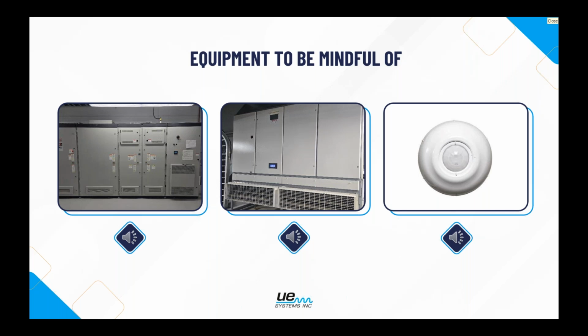The example that I have here in the middle is to be aware of fans especially. Here we have a fan in the room that, if we were not aware of it and had been inspecting other pieces of equipment, there was actually a damaged blade inside of this fan that was rattling around rather aggressively. And if that had reflected off another piece of equipment, it actually could have been mistaken for tracking, possibly with mechanical looseness and tracking in that sound file, depending on how close we were.